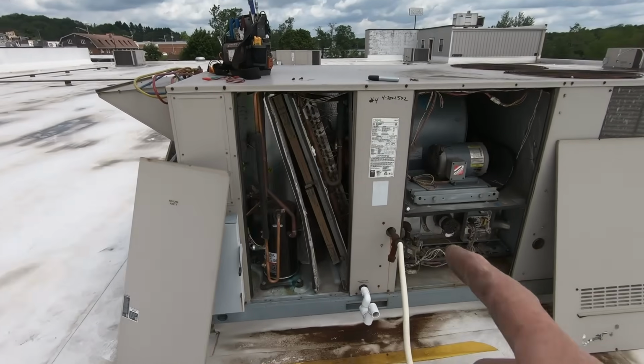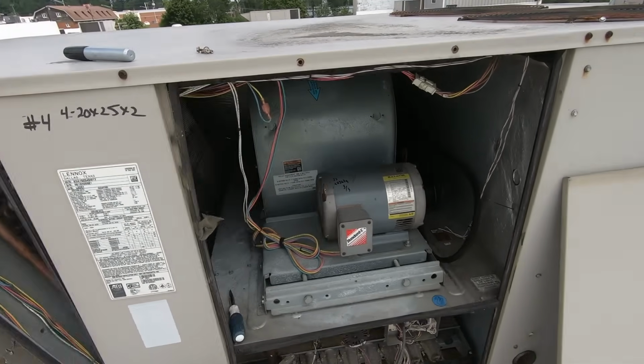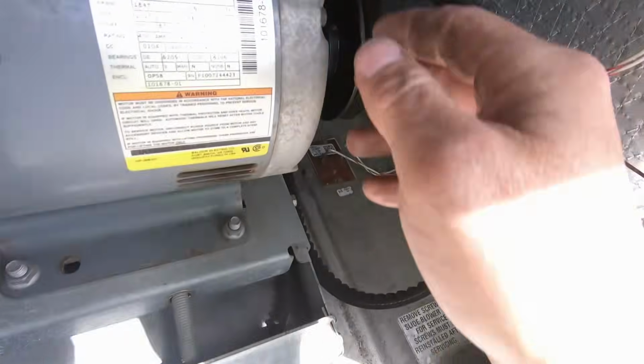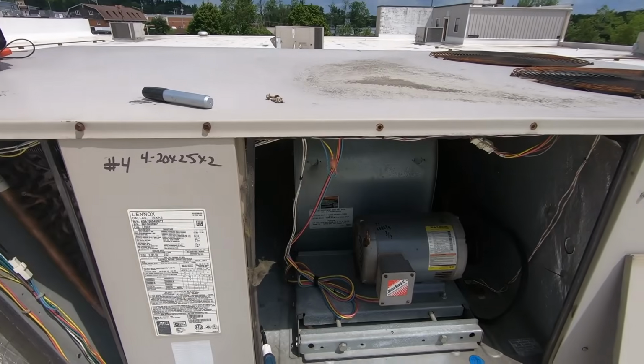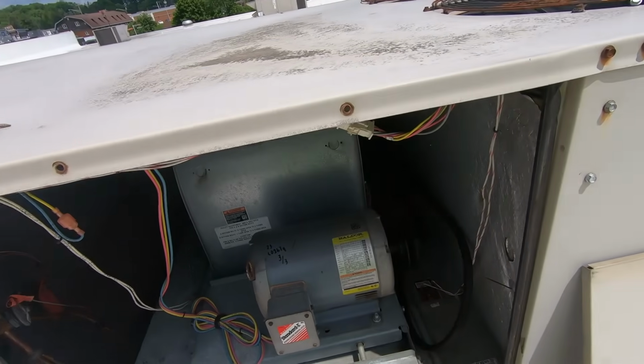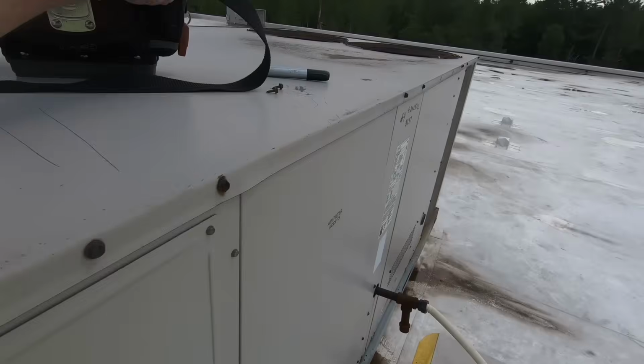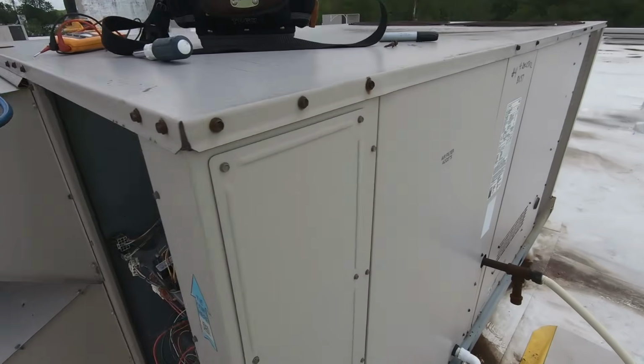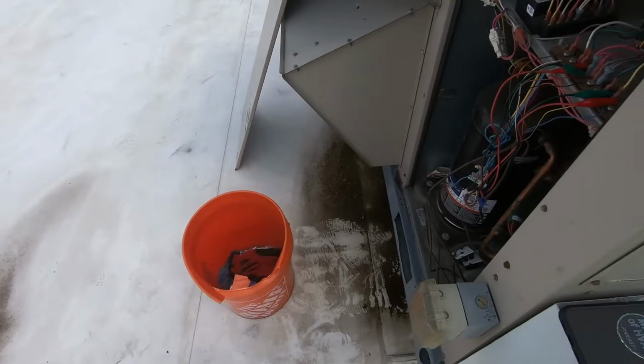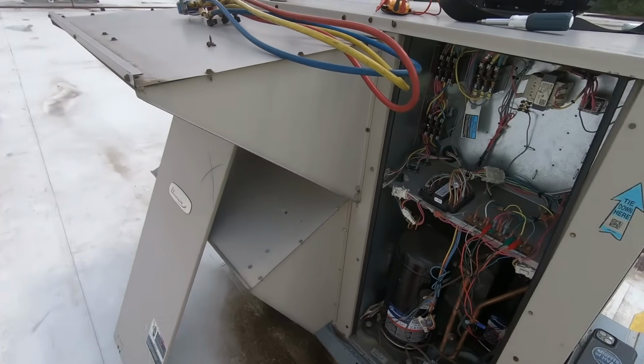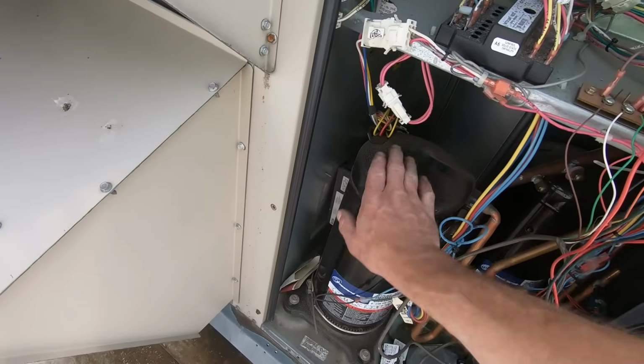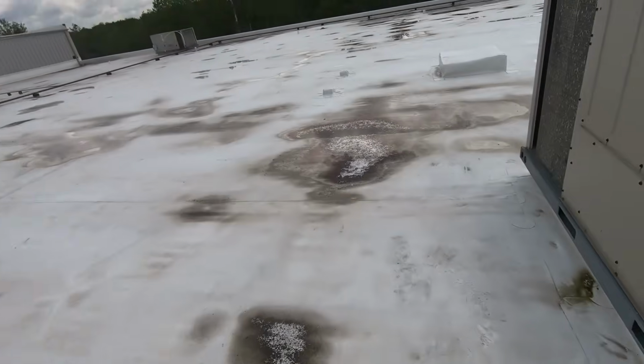All right, we're on number 4, and everything looks good except for the blower. I've got an extremely sloppy bearing. It's flopping around. I'm gonna recommend a blower rebuild. Whether they do it or not, it's up to them. Okay, here we are. Pretty much just the blower rebuild is all I found on this guy. Both compressors are running. Heat exchanger's good.